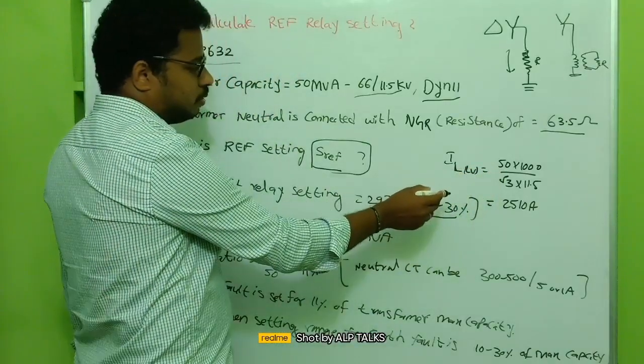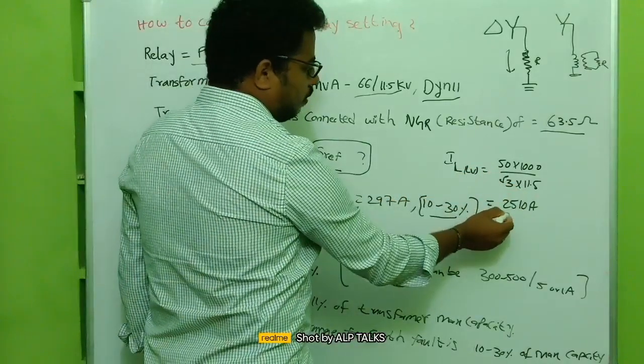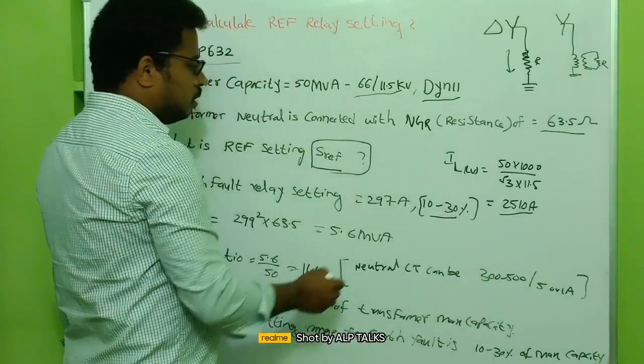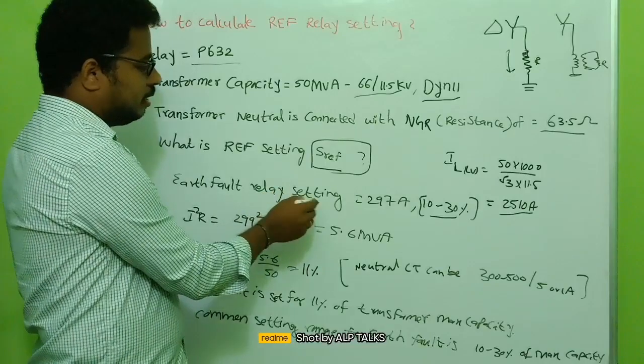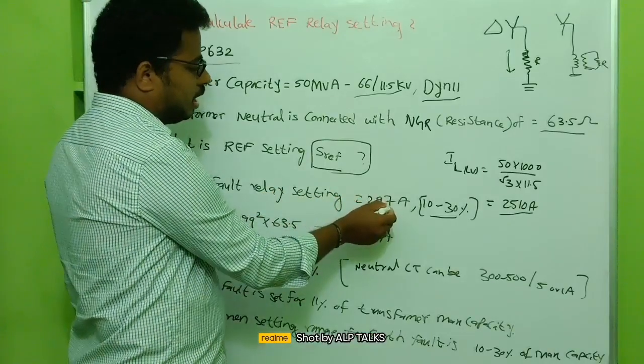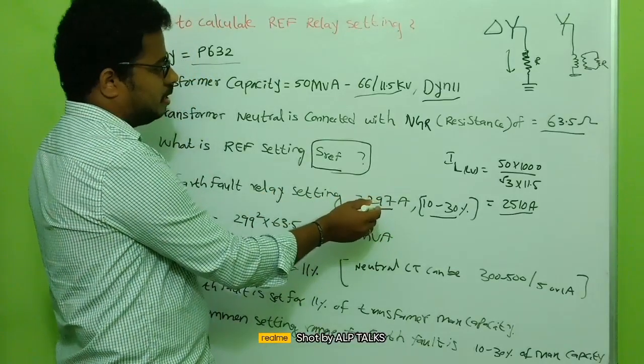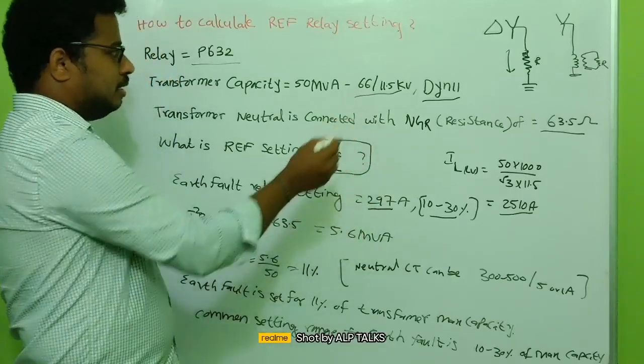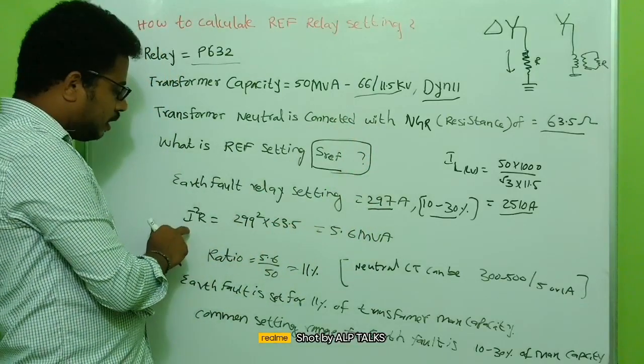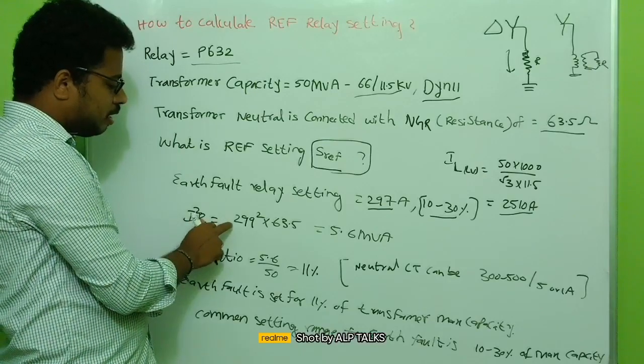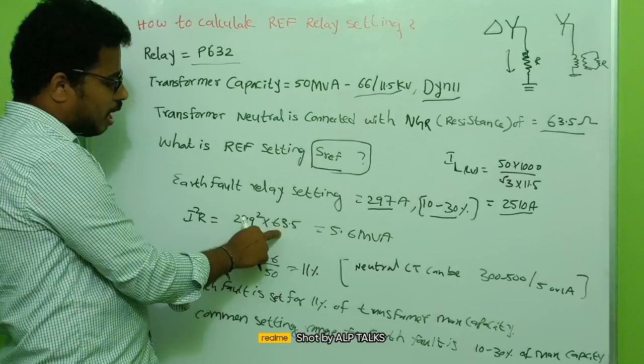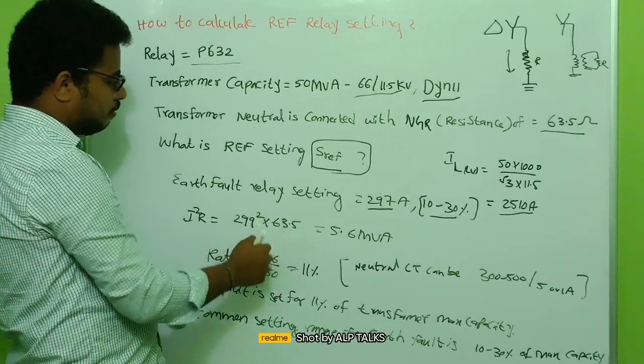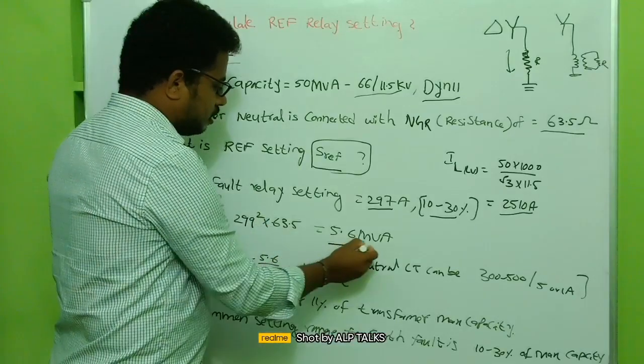50 times thousand by root 3 times 11.5, so you will get 2510. So generally 10 to 30 percent will be the fault relay setting. Let's take 297 ampere. 297 ampere, in this case they took 297 ampere. Let's calculate I square R, so here the I square R is nothing but 297 ampere square into the resistance we have, which is 63.5.